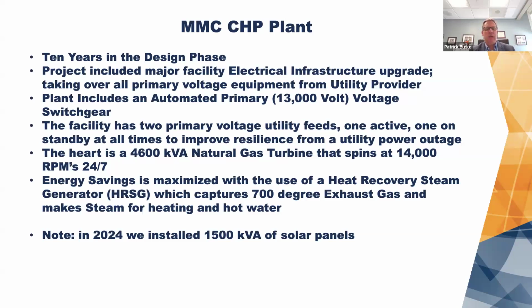During that process, we maintained two individual primary voltage feeds. One of them is active all the time, and the other one is on standby. That puts us in a position where we are less reliant on our emergency generators, and that's critical at a hospital because even though emergency power backs you up, there are certain functions like surgeries that you won't start when the hospital is on emergency power. So having a second utility feed that you can automatically switch to is really a nice luxury in terms of resilience and reliability.